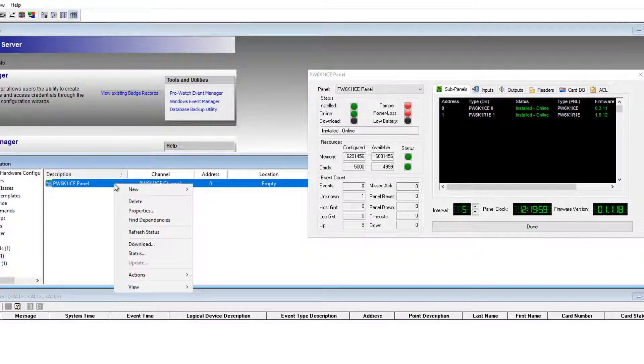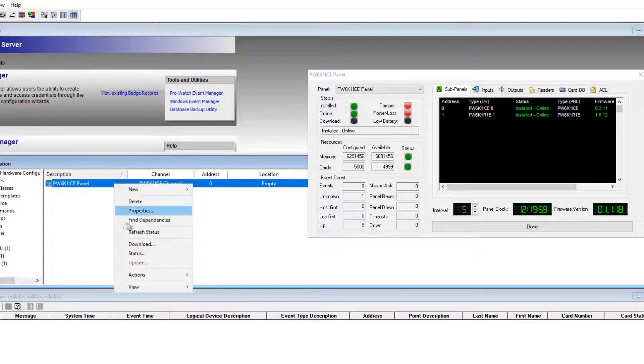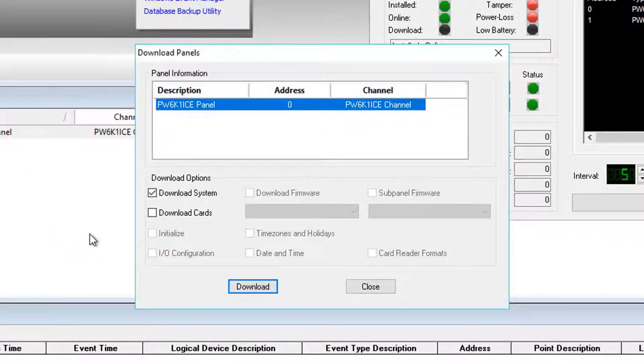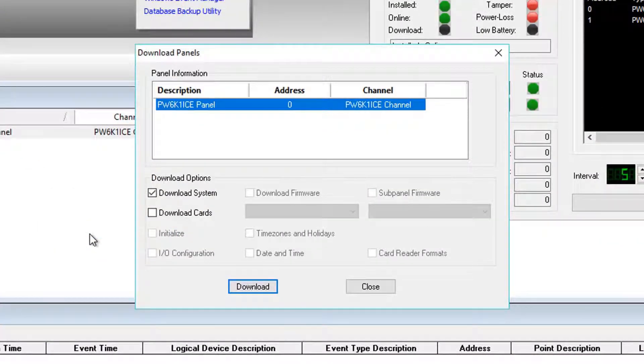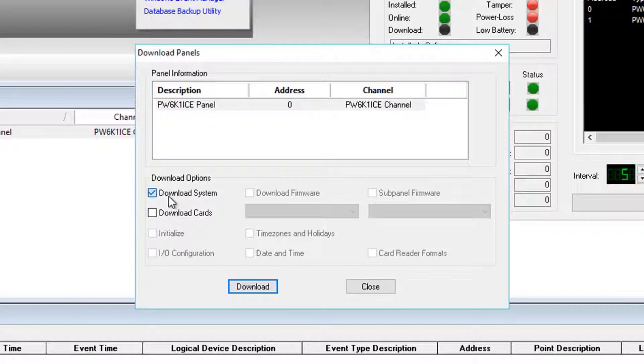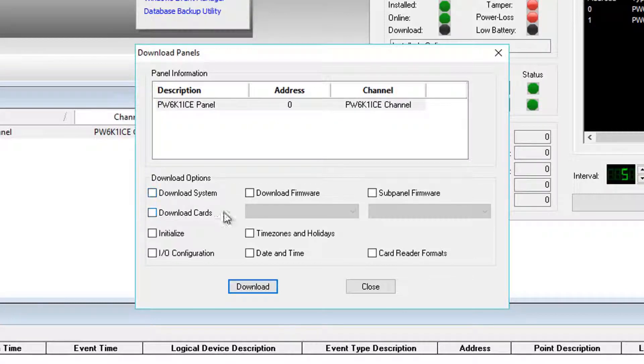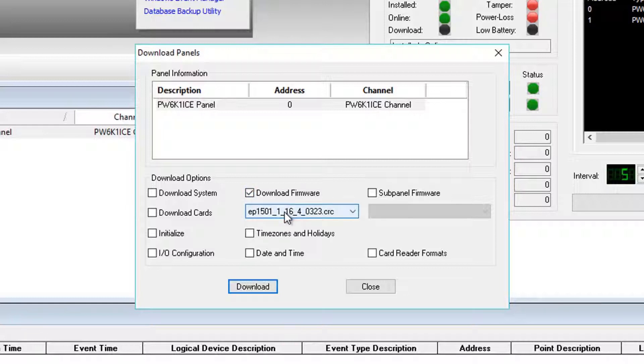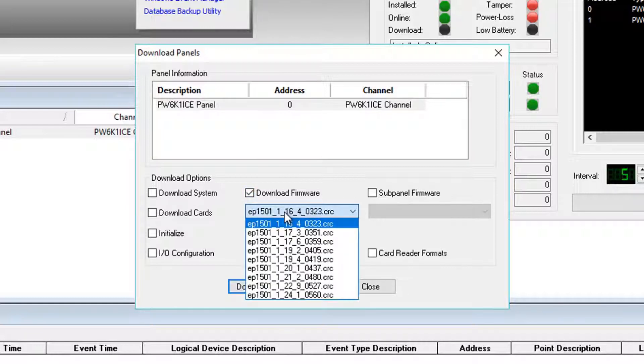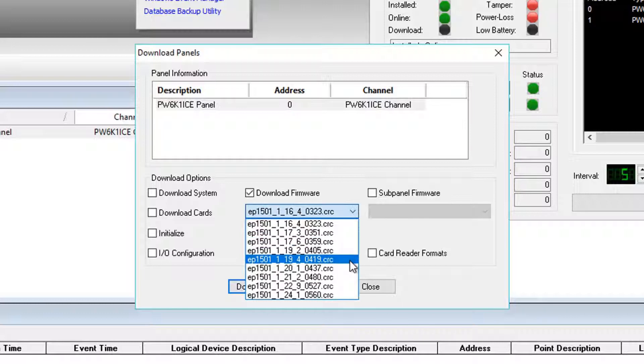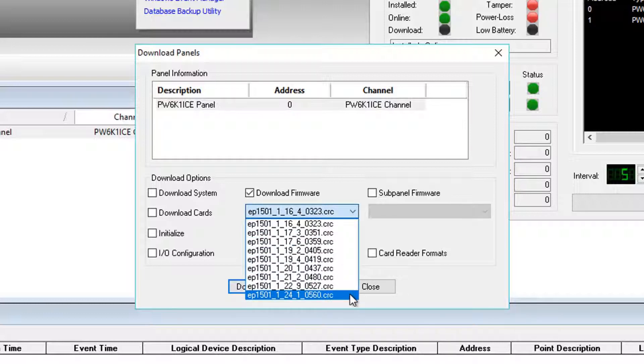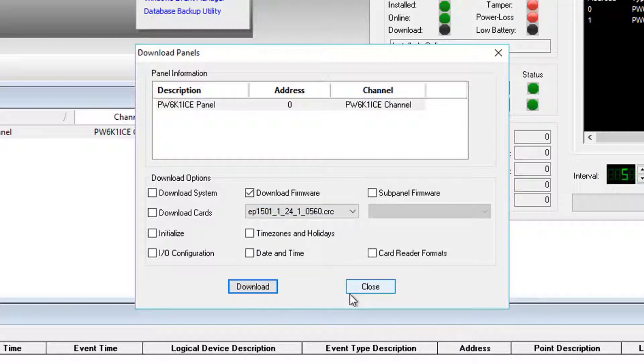To begin, right-click on the controller, select Download. Step one of three in the firmware download process is unchecking Download System and simply checking Download Firmware, and selecting the appropriate firmware version from the pick list. In this case, we'll select the newest version for the ICE controller 1.24.1, and click Download.